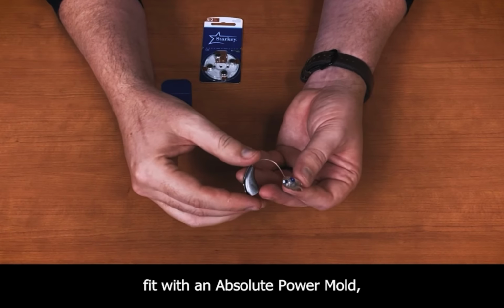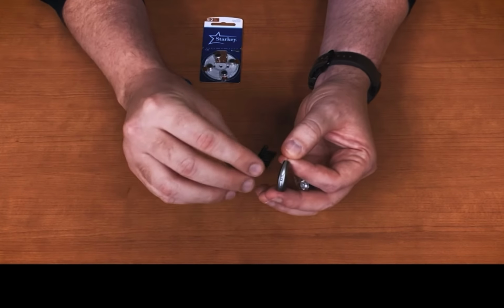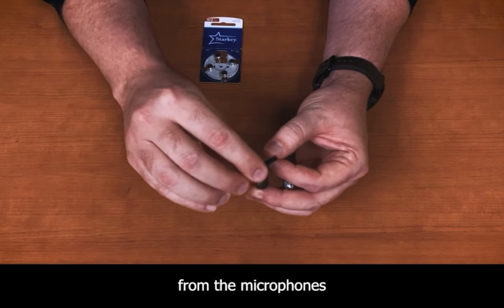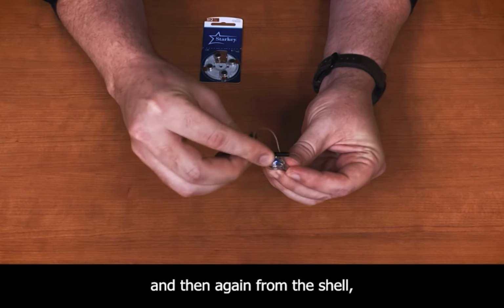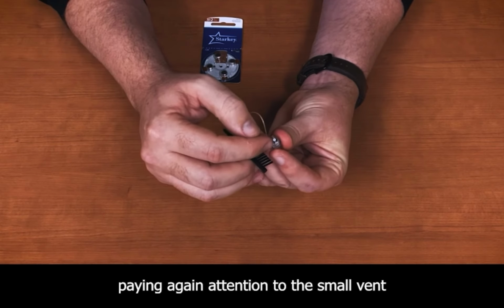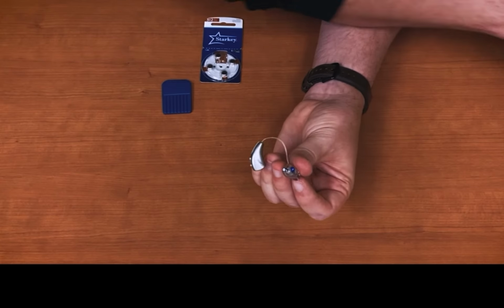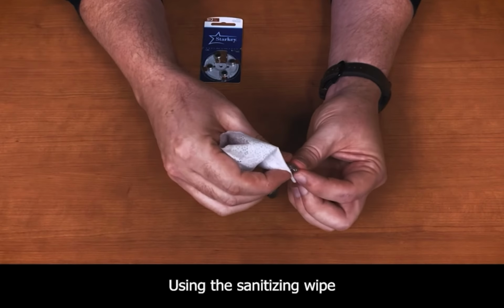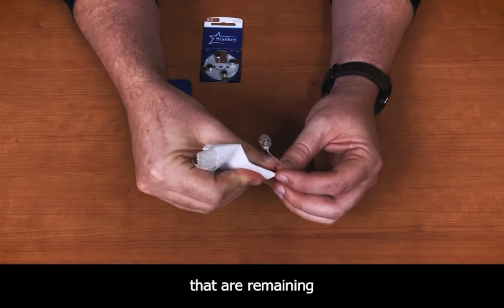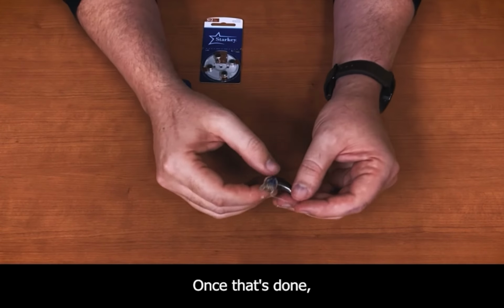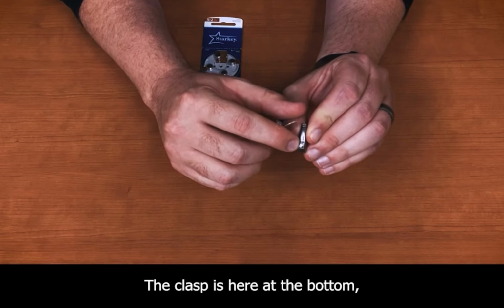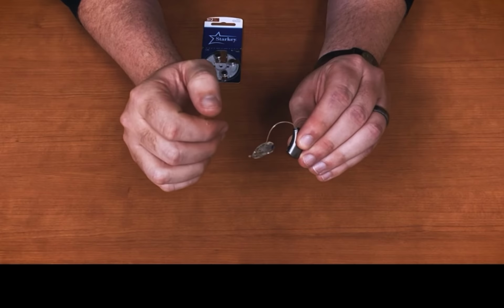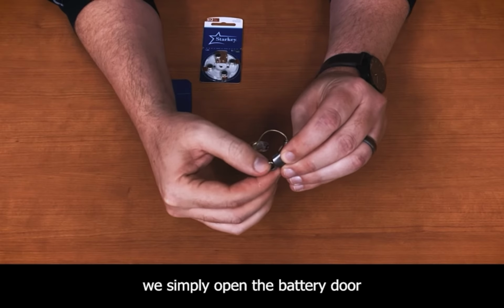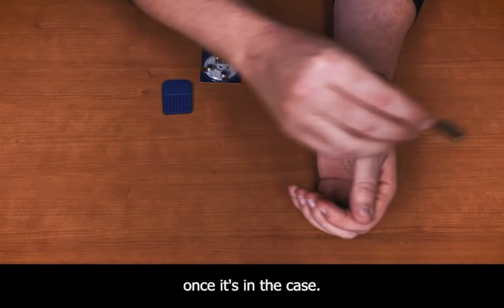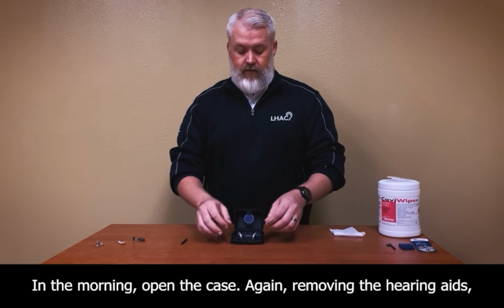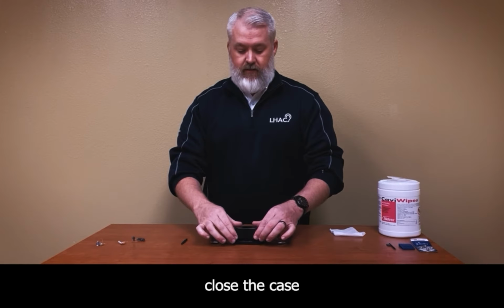If you are fit with an absolute power mold, using the brush, we're going to sweep away any dirt or debris from the microphones, and then again from the shell, paying again attention to the small vent at the bottom of the device. Using the sanitizing wipe, we'll clear any oils or wax that are remaining. Once that's done, we're going to open the battery door. The clasp is here at the bottom, generally on the inside curve of the hearing aid. Using a fingernail, we simply open the battery door, and we're done for the evening once it's in the case. In the morning, open the case, again removing the hearing aids, close the case, and they're ready to place on your ear.